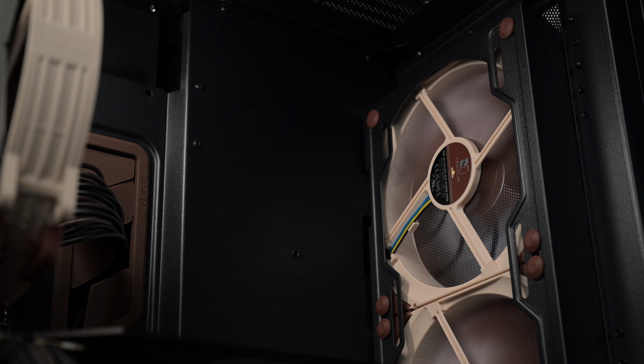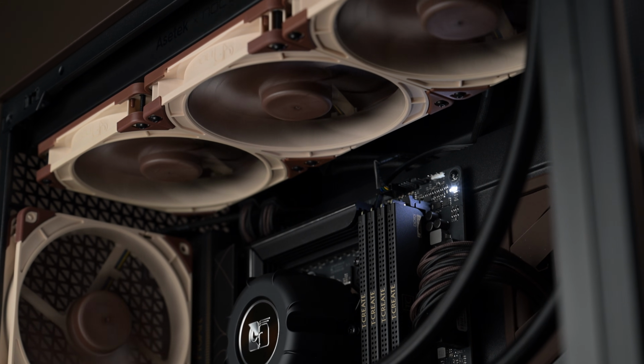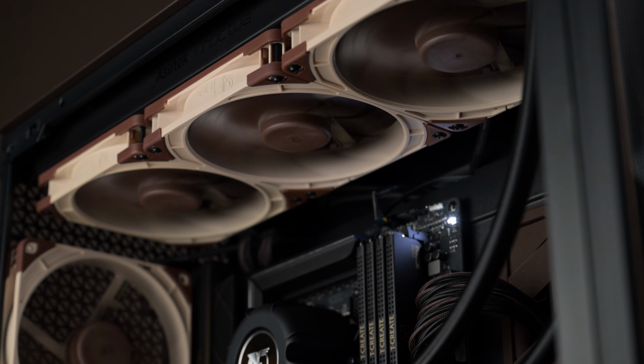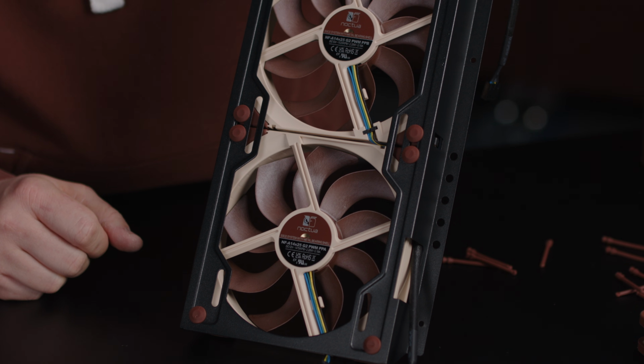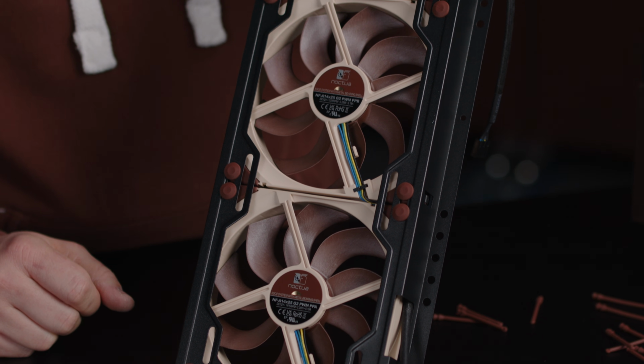Our G2 fans' acoustics are further refined by using speed offset variants to mitigate periodic humming or vibrations caused by beat frequencies. These undesirable harmonic phenomena can occur when running 2 fans of the same size next to each other at almost the same constant speed. By utilizing 2 different fan variants, a slightly slower one referred to as PPA and a slightly faster one labeled as PPB, and arranging them in an ABA sequence, the overall cooling performance can be kept the same, while preventing unpleasant acoustic interference.